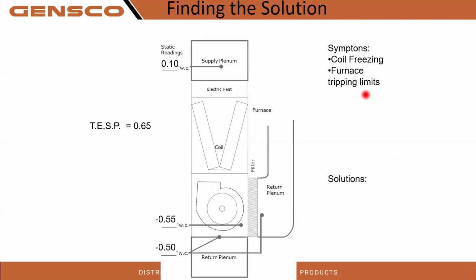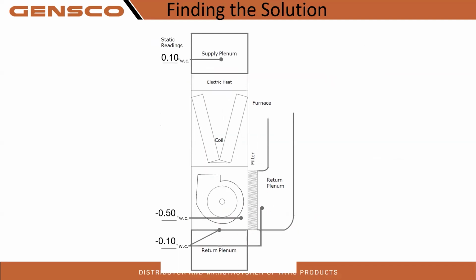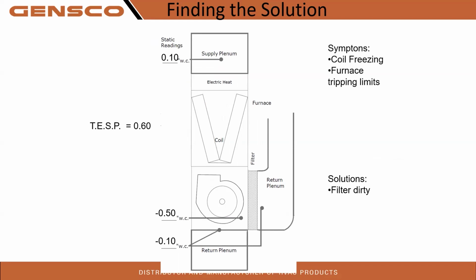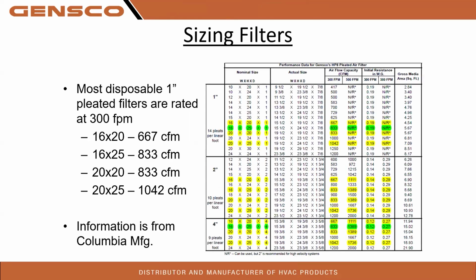Again, coil freezing, furnace tripping limits. This one, the return air is restricted. So we could have a plugged filter, we could have that sound liner came detached. I know I'm going through these pretty quick, but you guys get the idea on how important it is to check our static pressure.